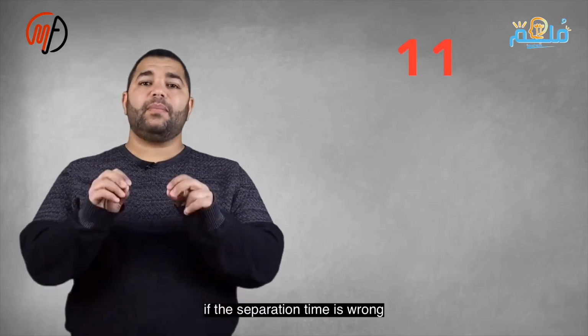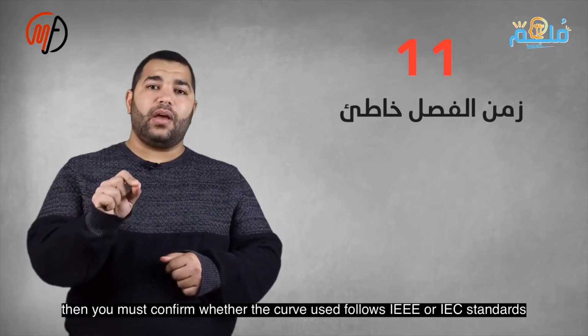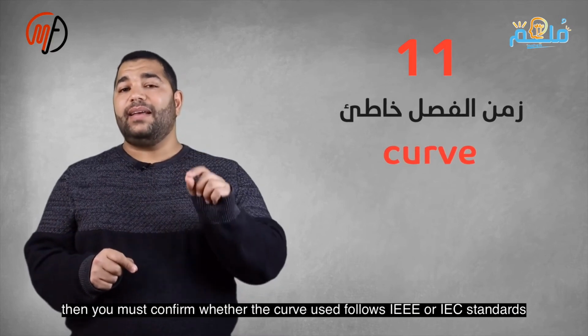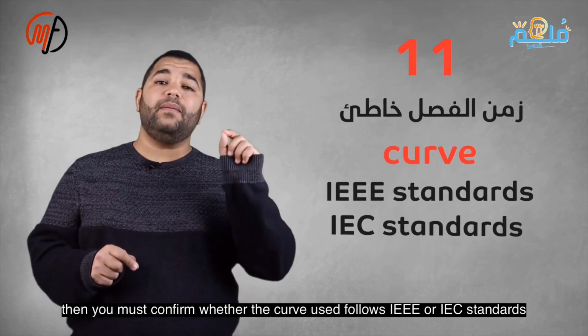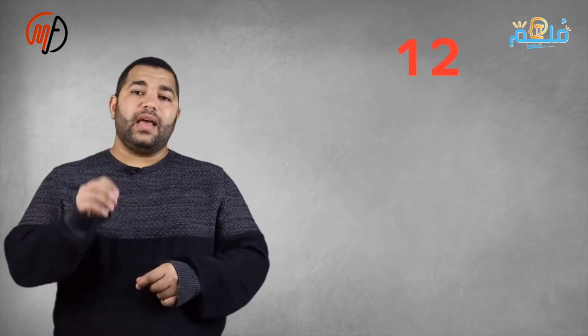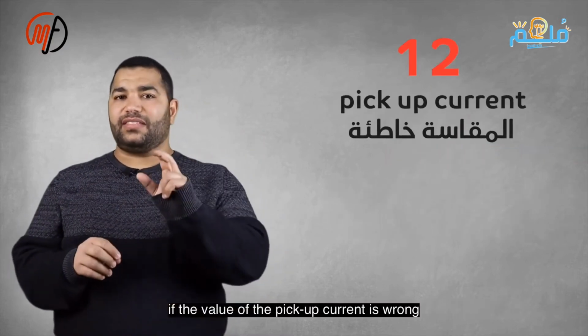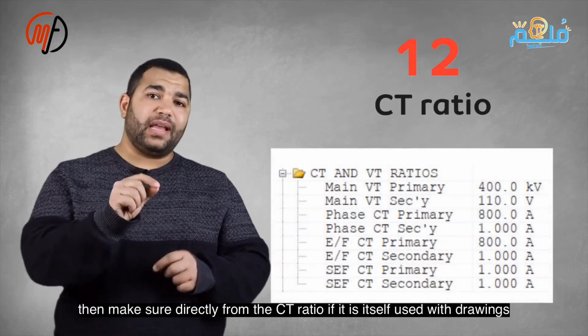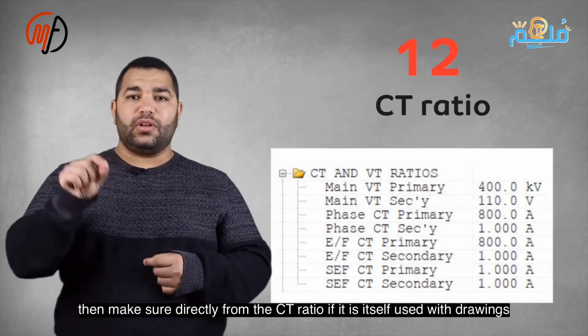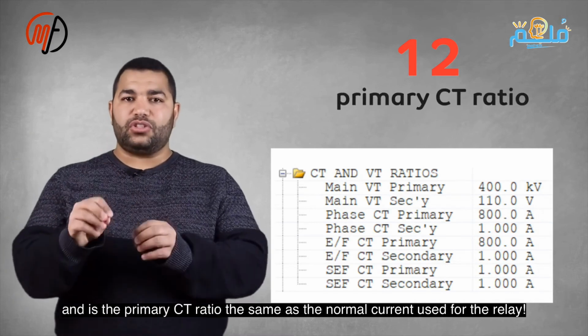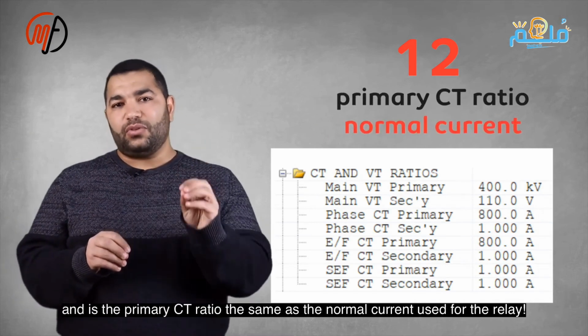11th, if the trip time is incorrect, you need to ensure that the curve being used adheres to either the IEEE standard or the IEC standard. 12th, if the measured pickup current value is incorrect, immediately check the CT ratio used in the relay to see if it matches what is shown in the drawing. Also, verify if the primary CT ratio is the same as the normal current used in the relay.